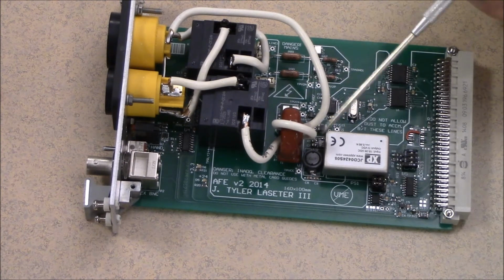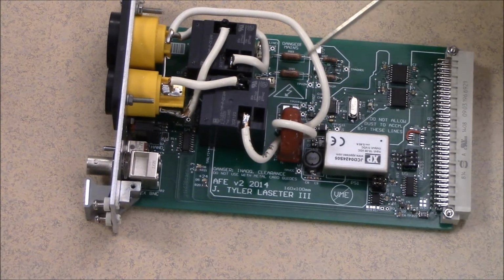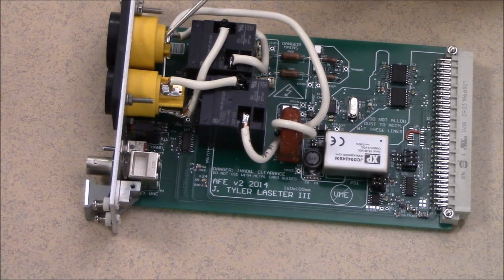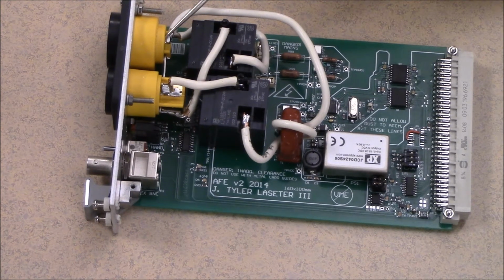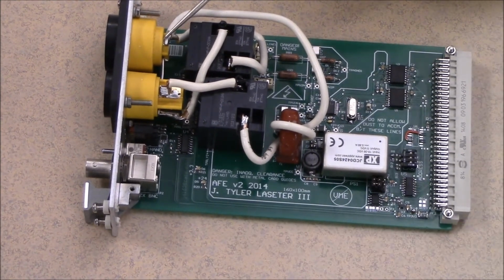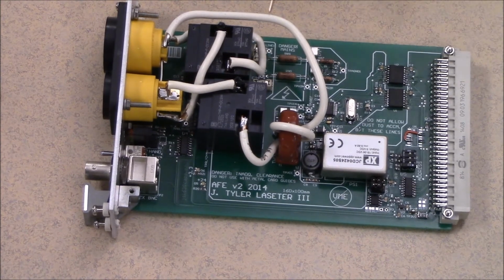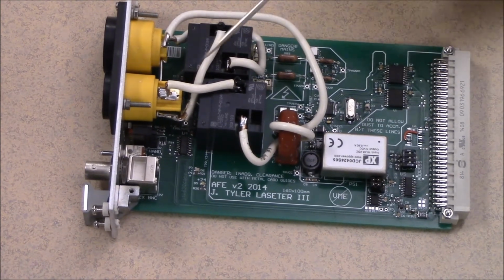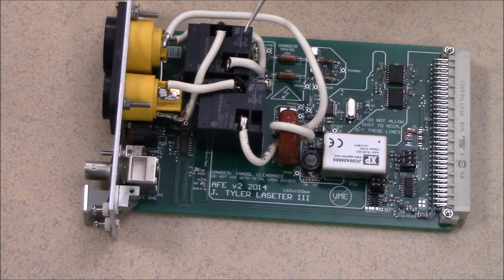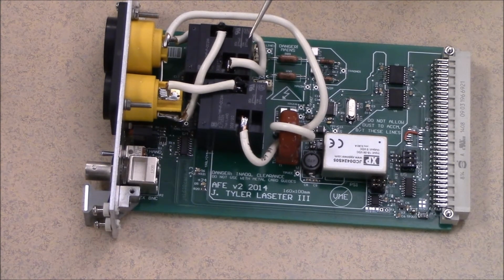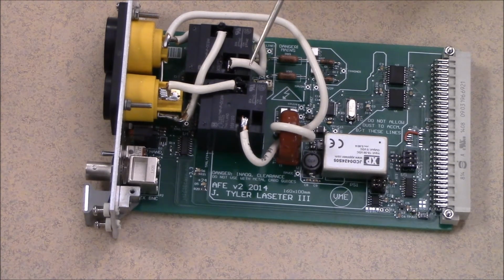The current takes 2 turns through this current transformer before exiting again at the measurement output for connecting the load under test. The voltage is picked off before the relay so that the voltage of the line can be measured regardless of whether or not the load is connected. This is useful as you can determine the line impedance of the building or location where you are measuring your devices based on the voltage drop incurred per a specific load applied.